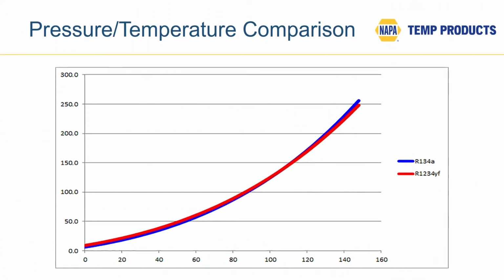Now, the good news, from a diagnostic and service perspective, is that the pressure temperature profile of these two refrigerants is virtually identical. You can see the blue line is R134A, the red line is R1234YF. And so if it didn't say R1234YF on the gauges, just looking at high and low side gauge pressures, you would never know whether you're working on an R1234YF or an R134A system. So that's the good news from a diagnostic and service perspective.